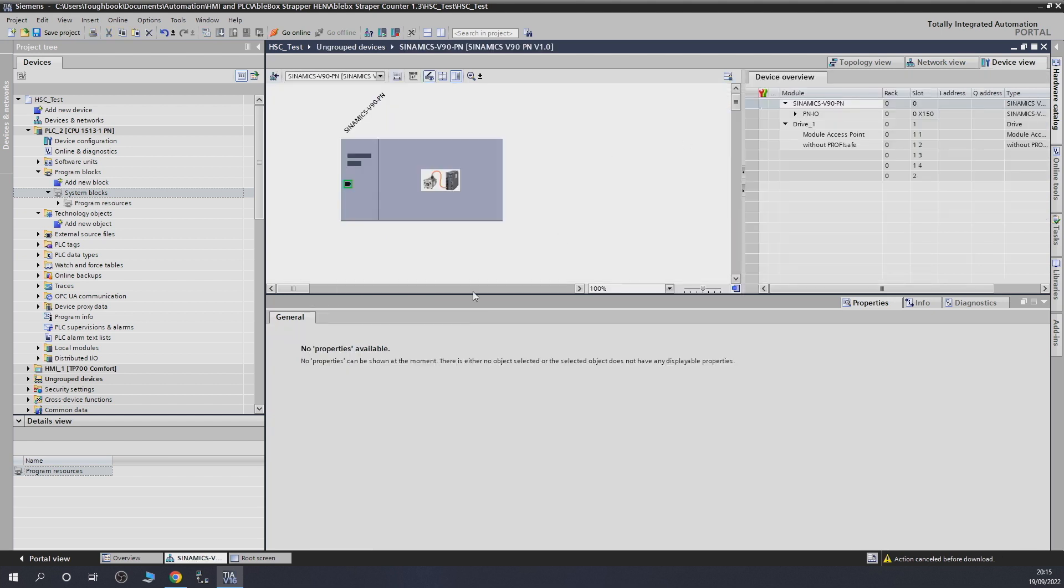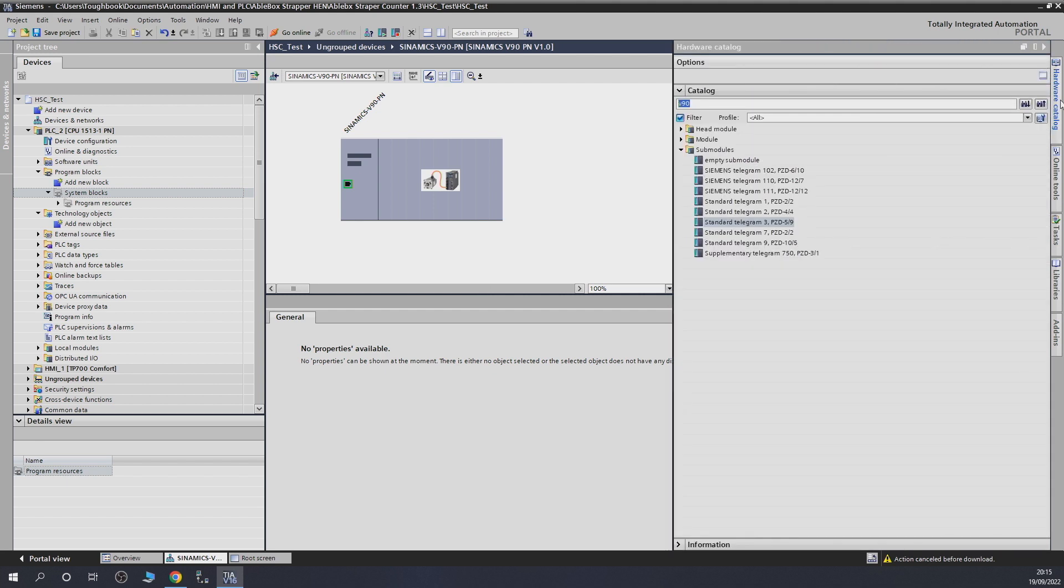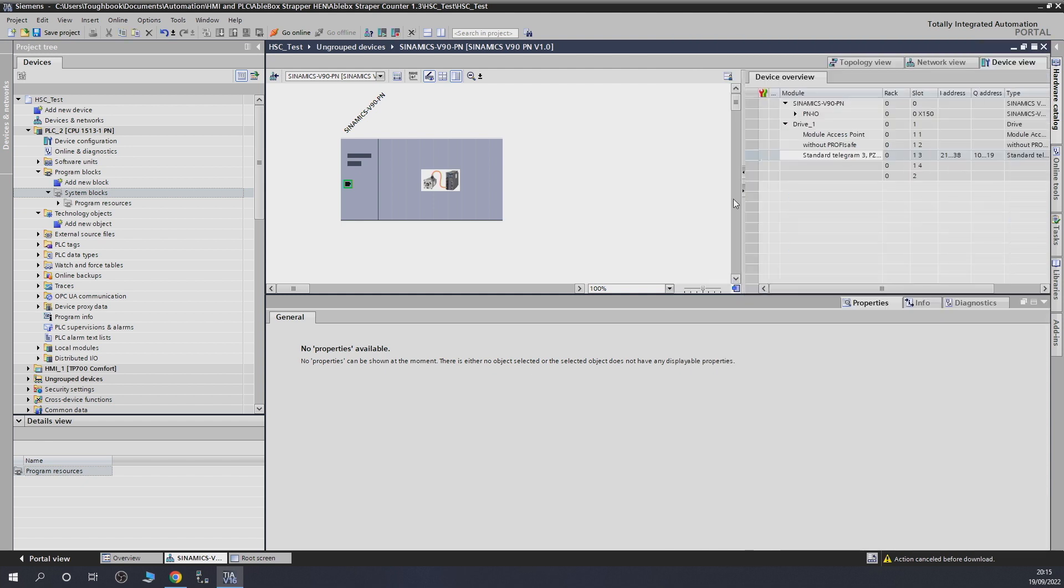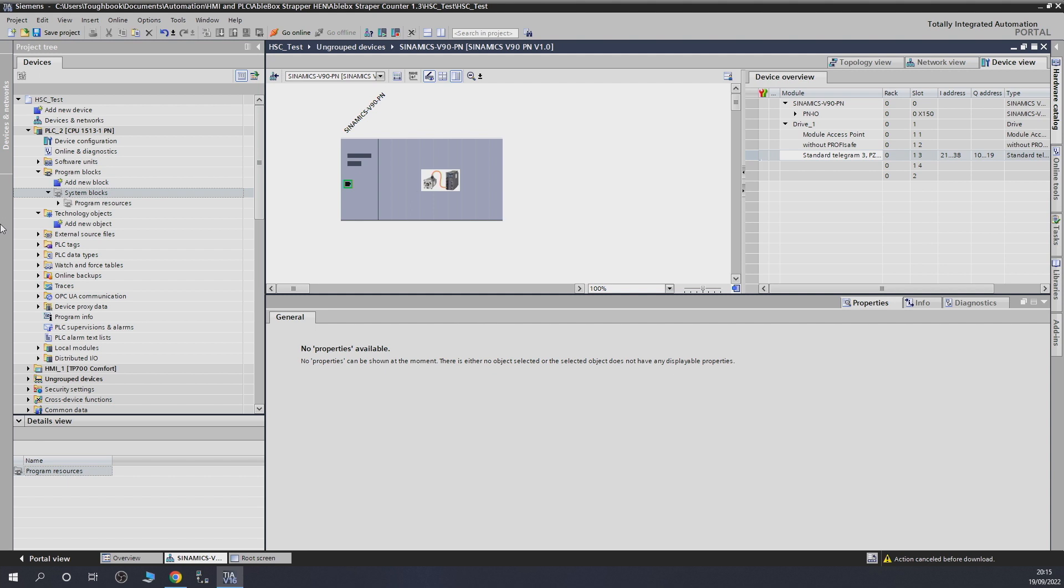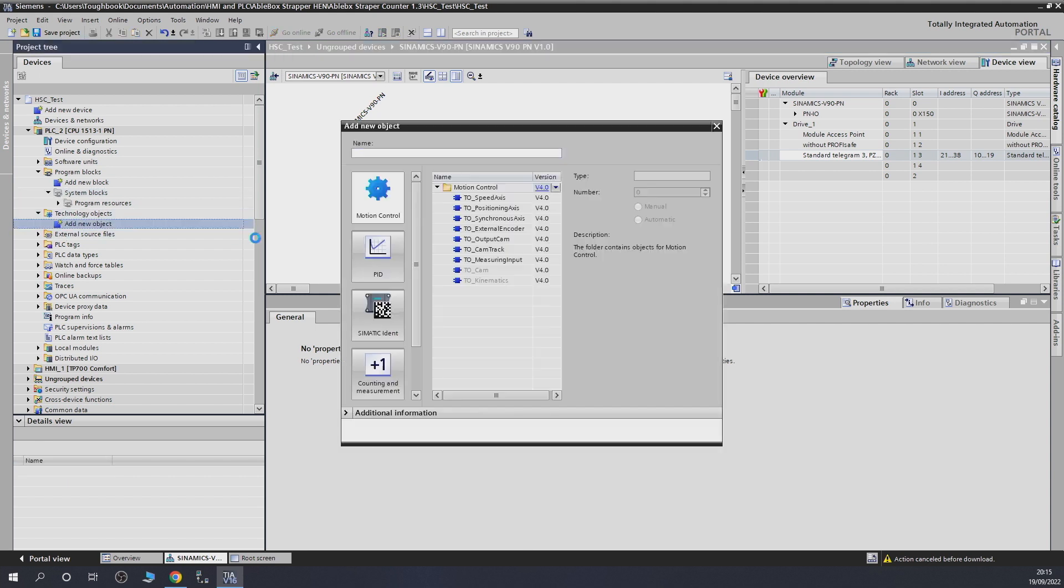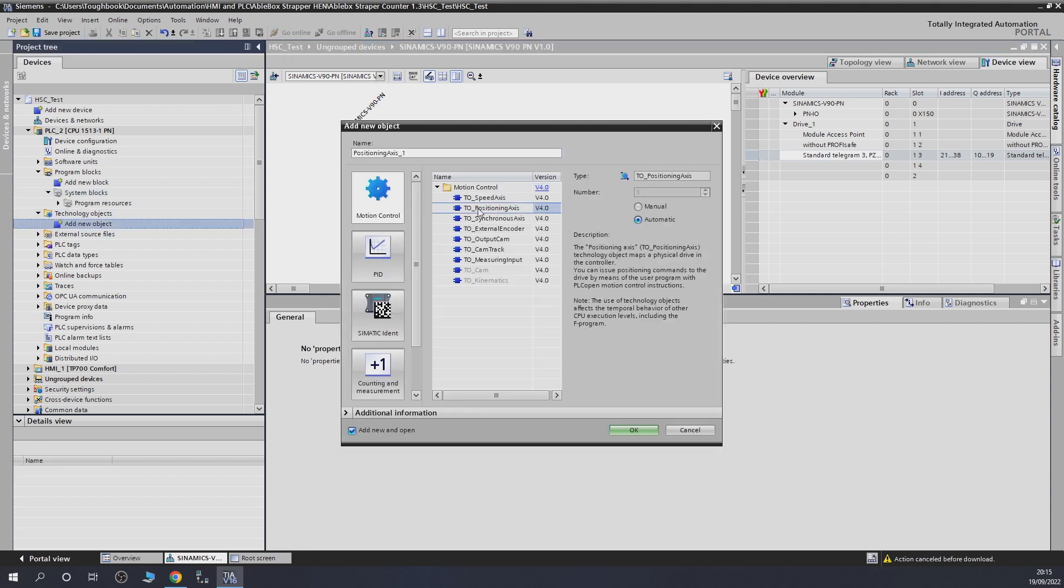Remember, if you haven't watched the previous video, I suggest you watch it. We need to give it a telegram. Let's go into hardware catalog. As you can see, third telegram, that's what we set up in the drive in the last video. We're going to give the drive in the project that telegram they can be talking to. It's very important. Once we've done that, telegram comes in here. From there, we're not going to do anything in here yet. What we're going to do is create a technology block.